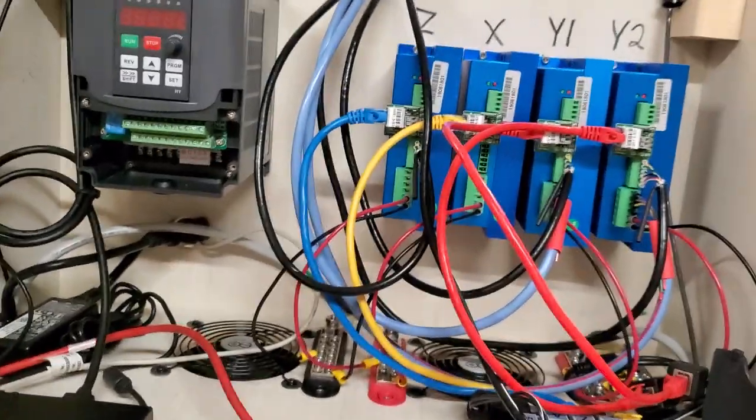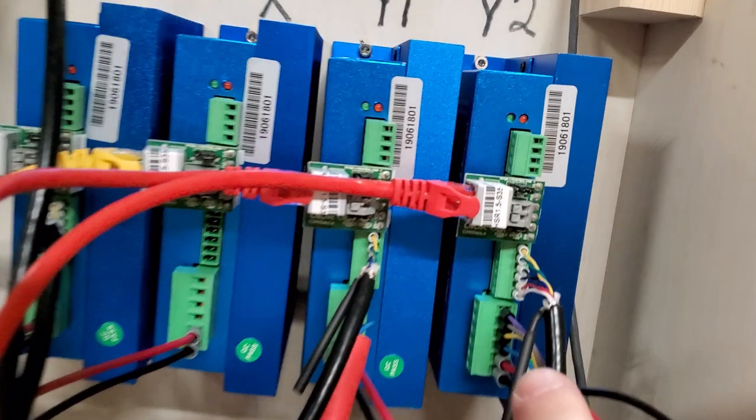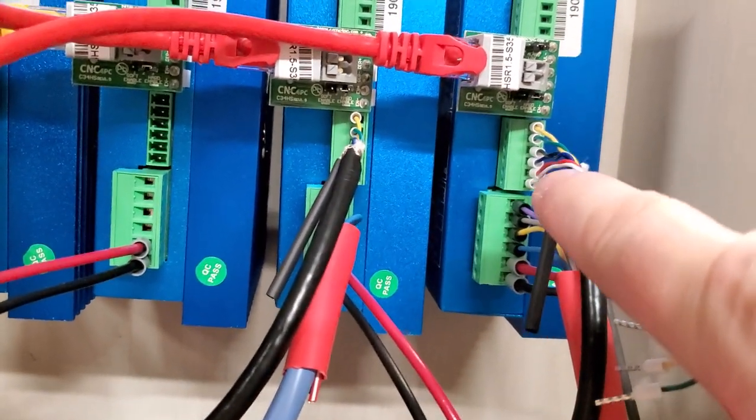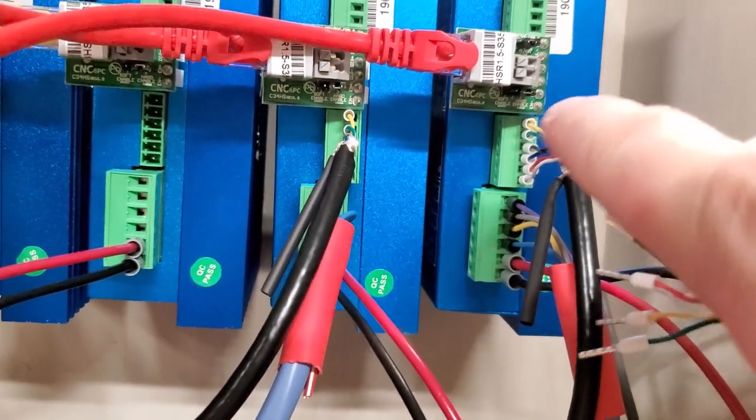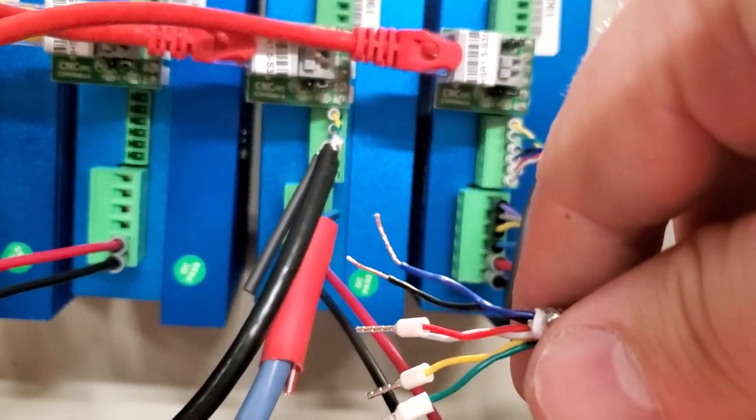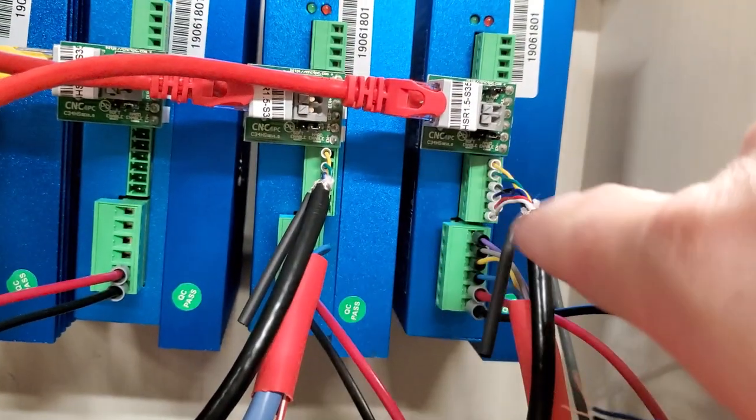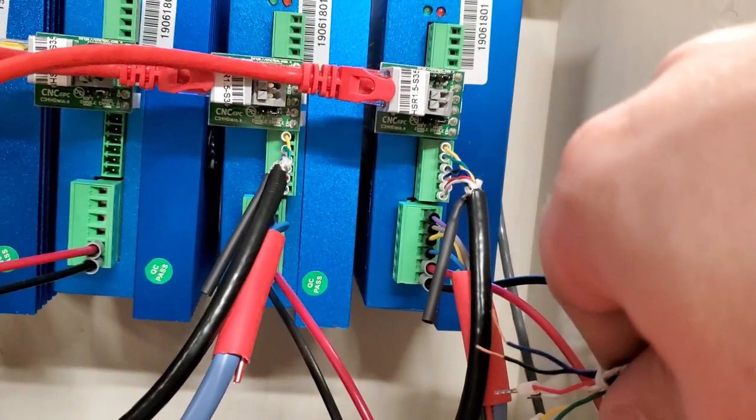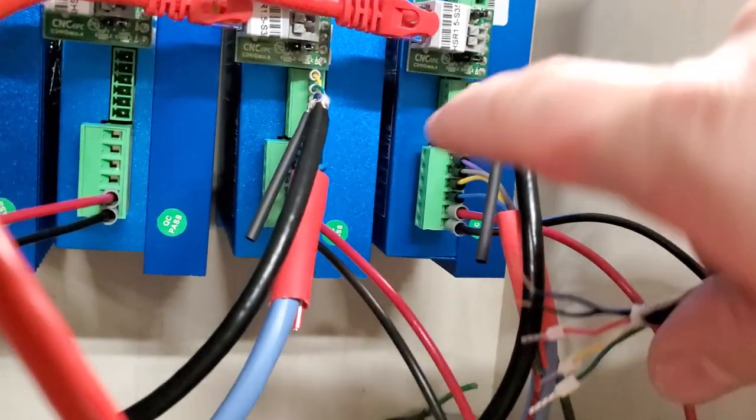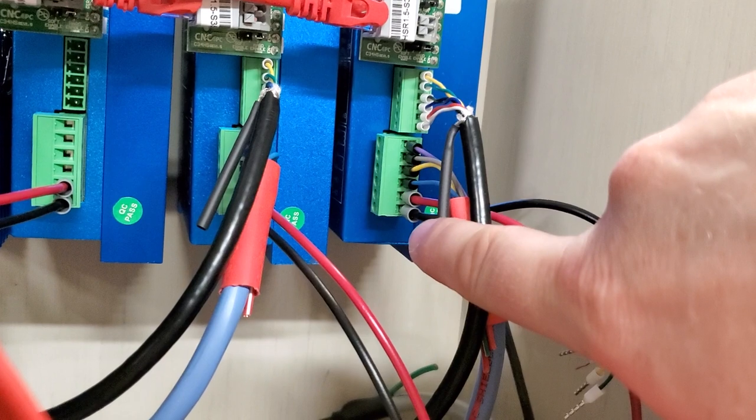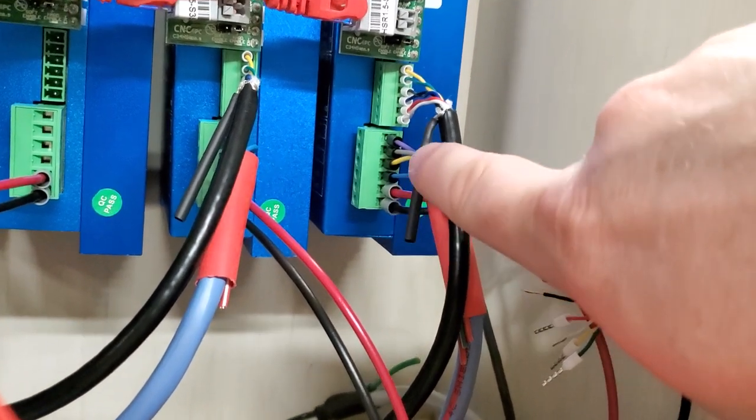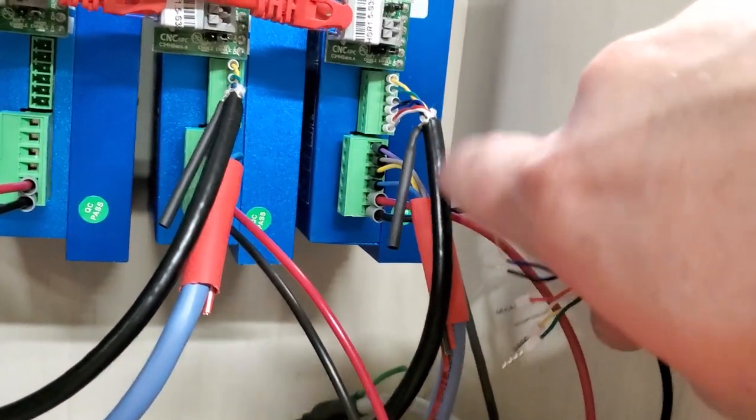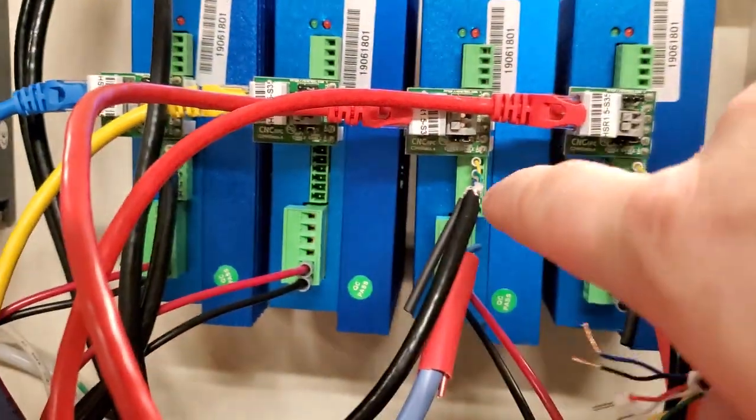One of the advantages to ferrules is that it keeps your wires nice and organized. You can see them right there. I don't have to worry about little splinters of copper going into the port next to it, shorting it out, causing errors later on. They crimp in very nicely. You can see I've got different gauges. I've got some large ones right there, some medium, and some really small ones.